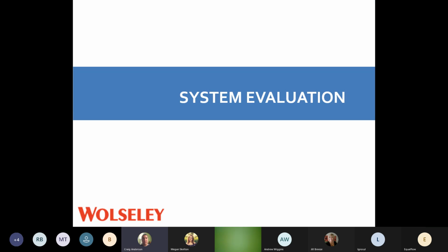So, system evaluation. This is our final documentation. You've done your nitrogen tests, you've done your vacuum, we have our low voltage, our coils in properly, we're ready to go, we're ready to turn this air conditioner on. If you don't have a startup sheet, start filling one out. They're available online. We want to document static pressure, our low side or high side gauges, electrical going to the unit. We want to know what's going on with that unit.